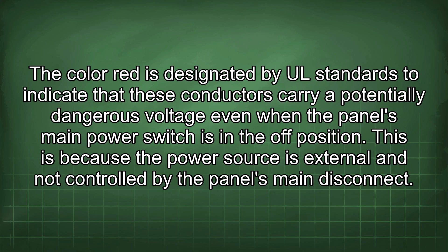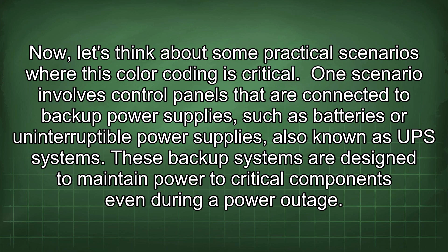Now, let's think about some practical scenarios where this color coding is critical. One scenario involves control panels that are connected to backup power supplies, such as batteries or uninterruptible power supplies, also known as UPS systems. These backup systems are designed to maintain power to critical components even during a power outage. In such cases, the DC conductors from the battery or UPS will remain energized, and they must be clearly identified with red insulation.